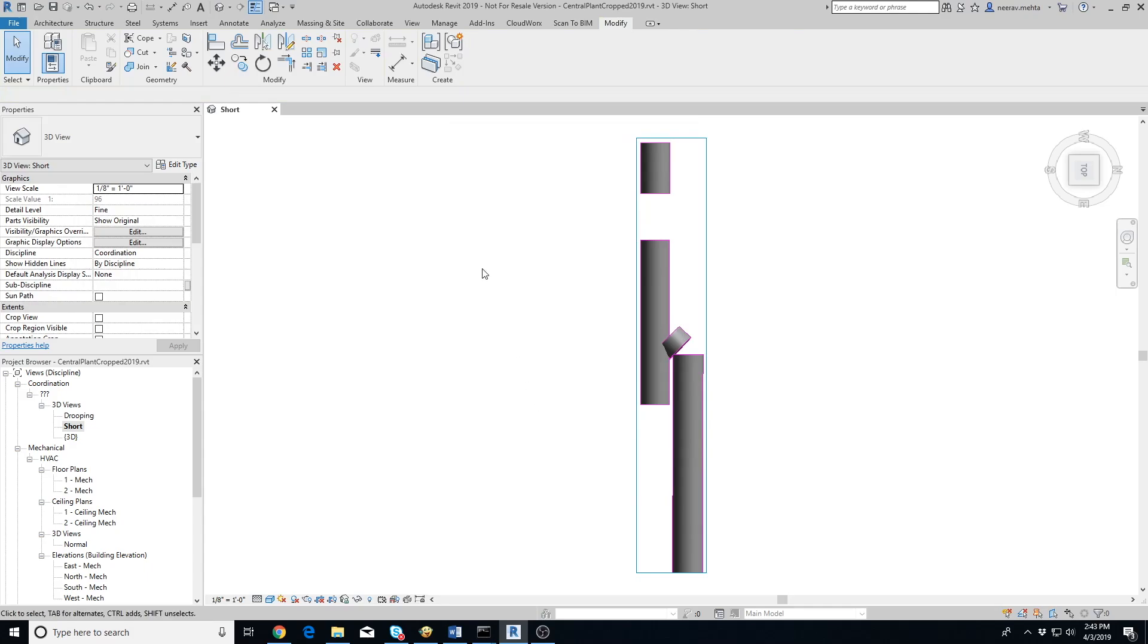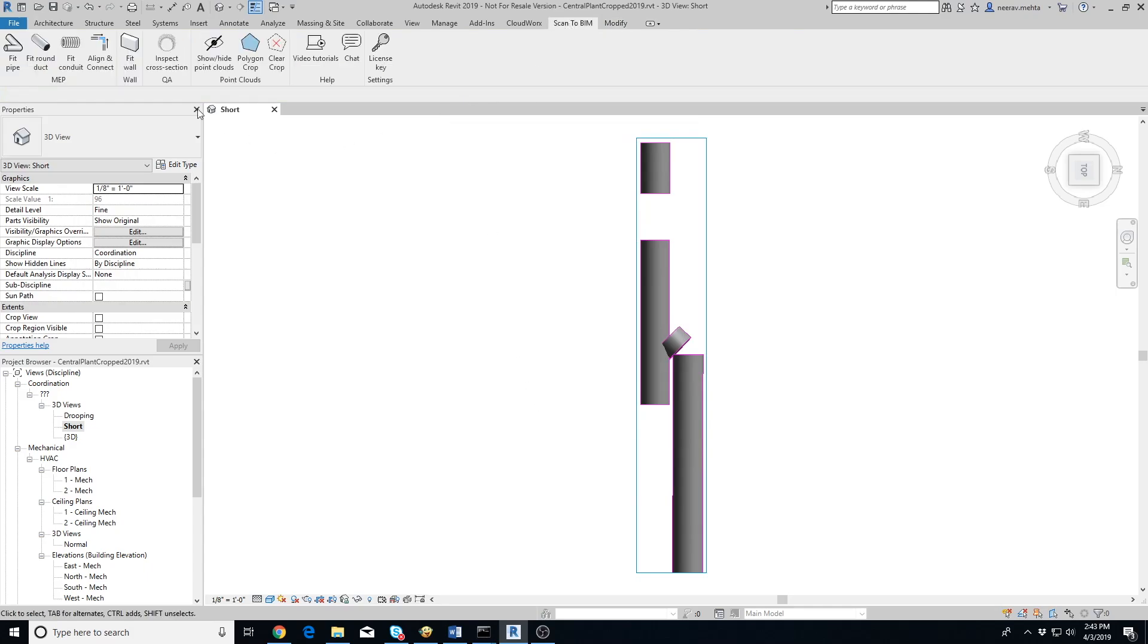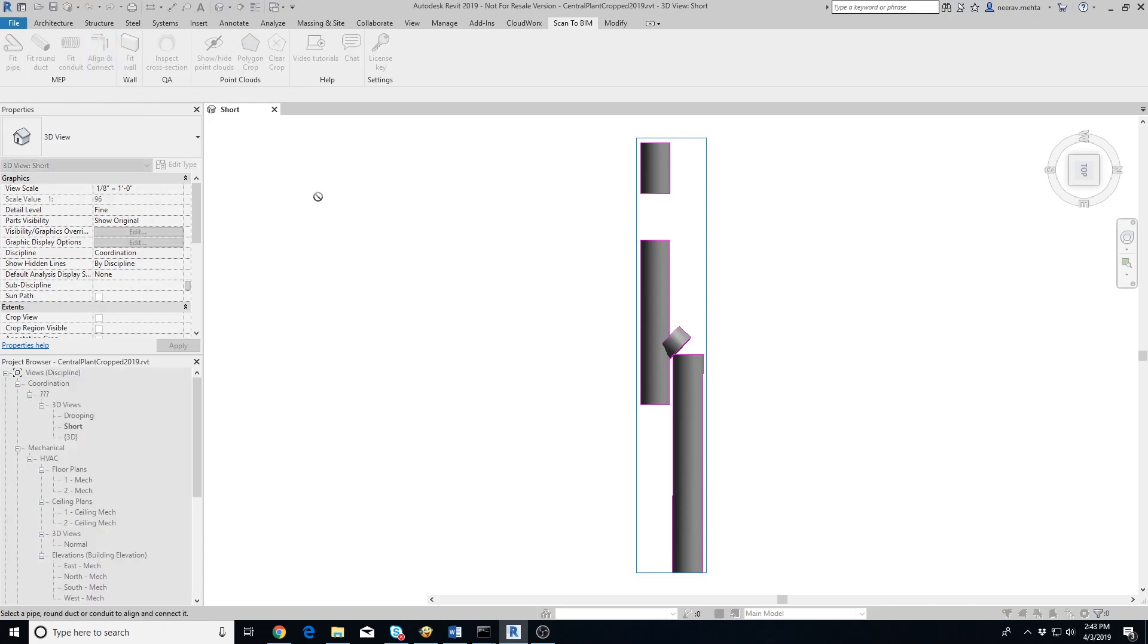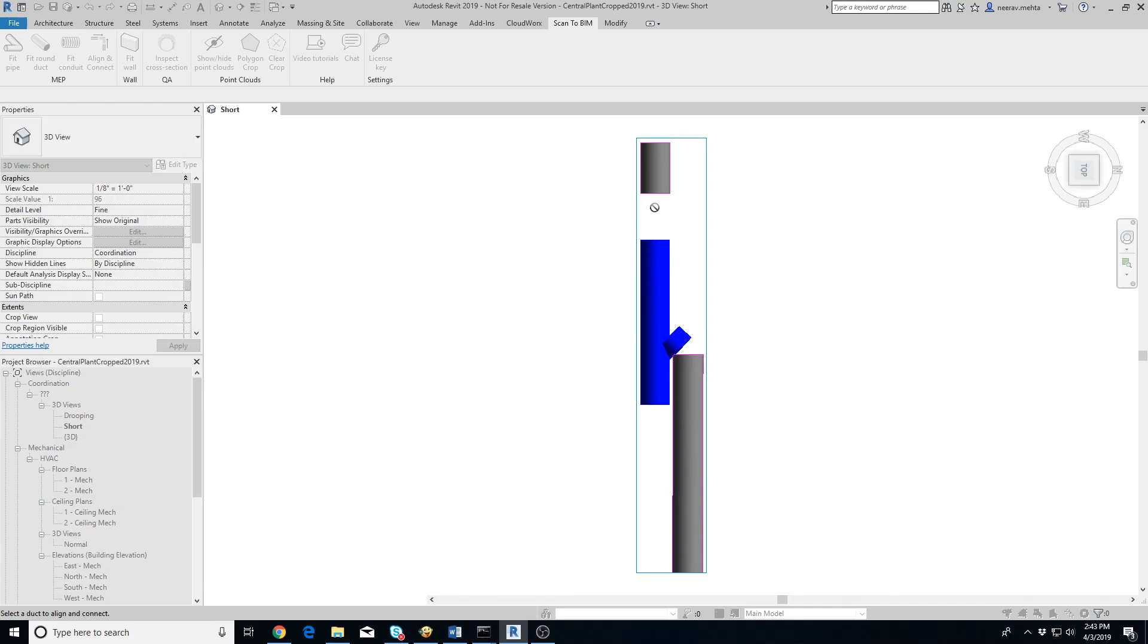To connect the ducts, click on Align and Connect button. Then select all the ducts in a run that you want to connect. Make sure to select them in the same order in which they are supposed to be connected. In other words, Duct 1 will connect to Duct 2, Duct 2 will connect to Duct 3 and so on. Once you are done selecting all the ducts in a run, press Escape.